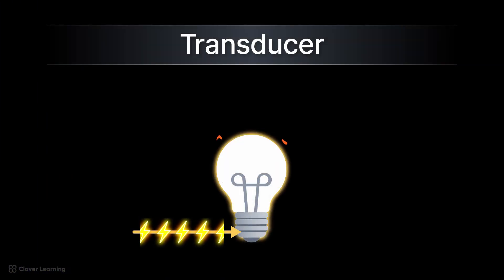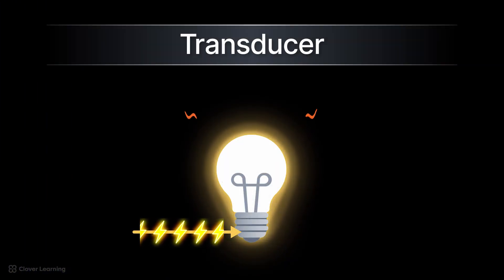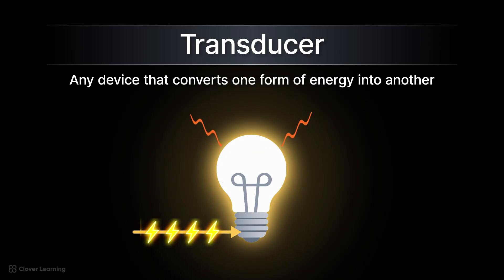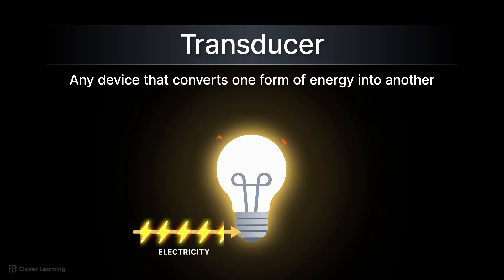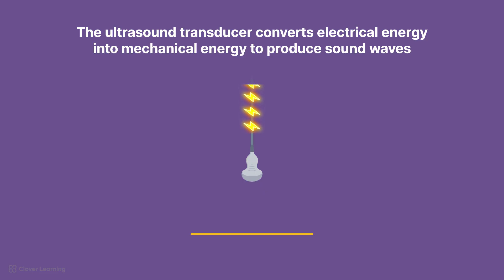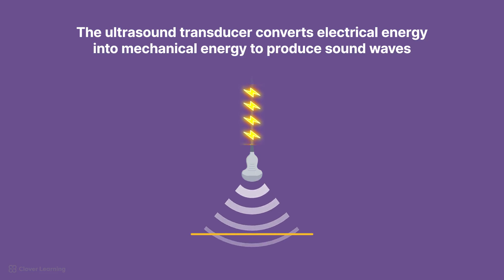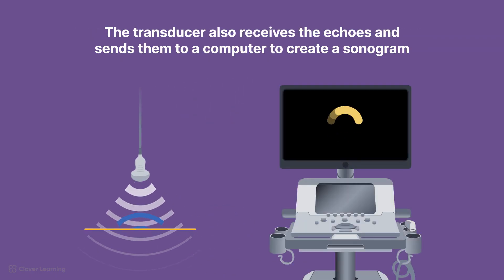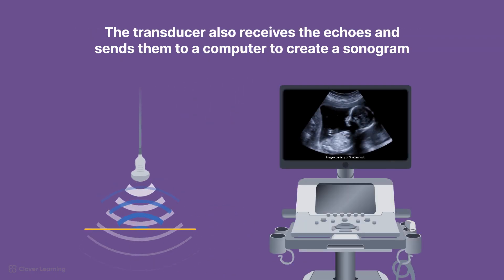Let's start by defining transducer. A transducer is any device that converts one form of energy into another. For instance, a light bulb is a transducer because it converts electrical energy into light and heat. In ultrasound imaging, the transducer is the key device which converts electrical energy into the mechanical energy that produces the sound waves, which bounce off body tissues and make echoes. It also receives the echoes and sends them to a computer that uses them to create a sonogram.